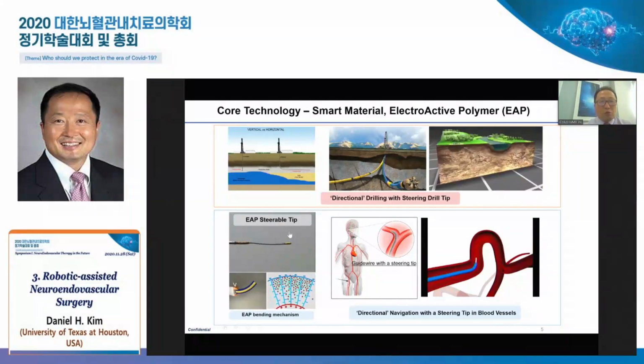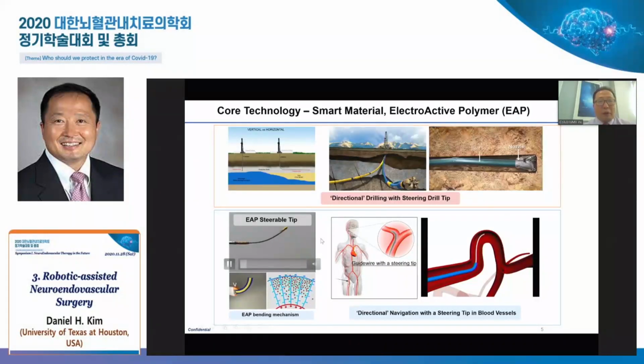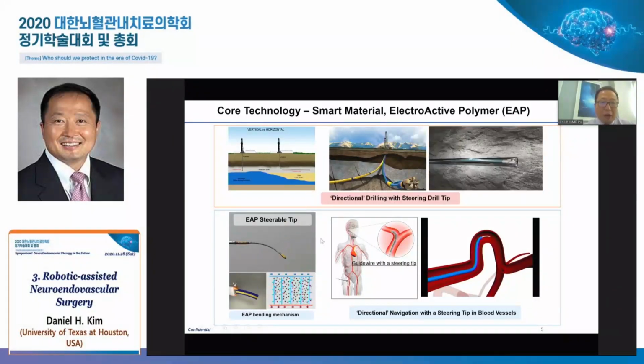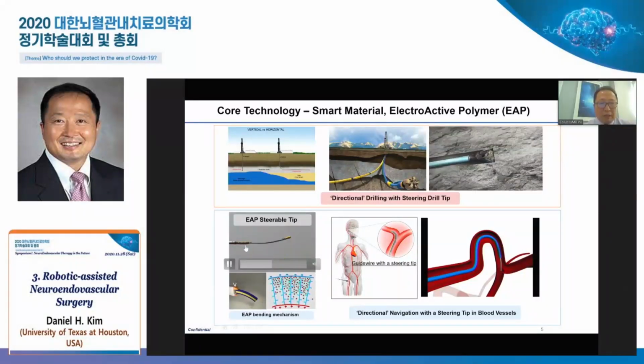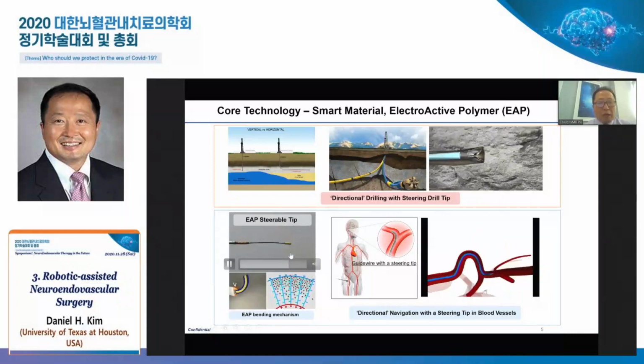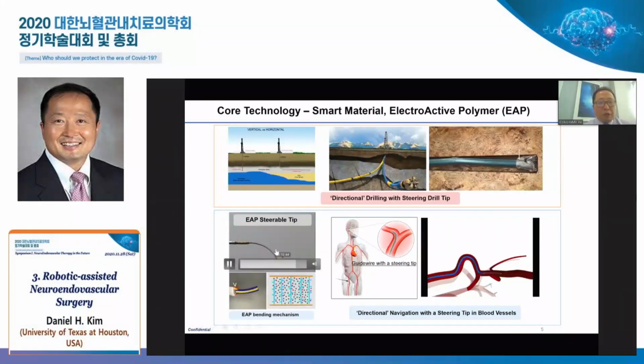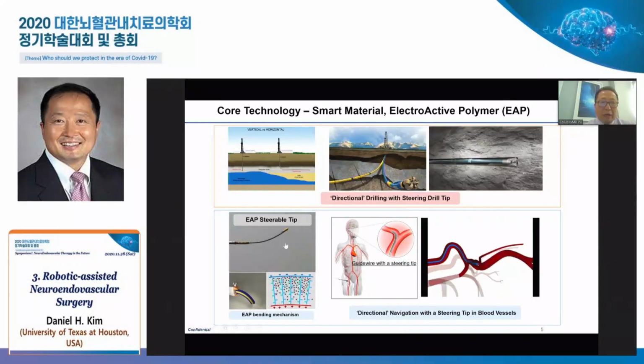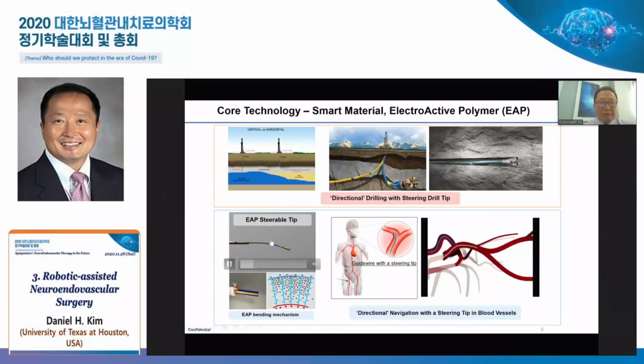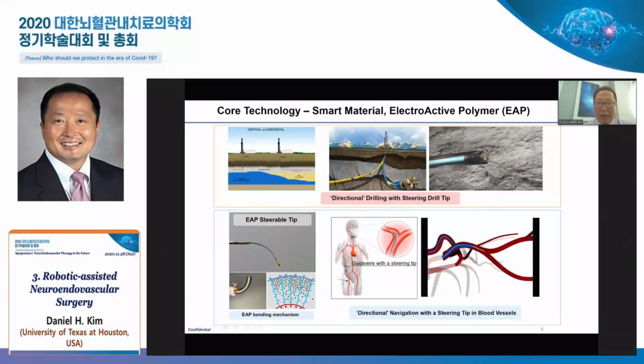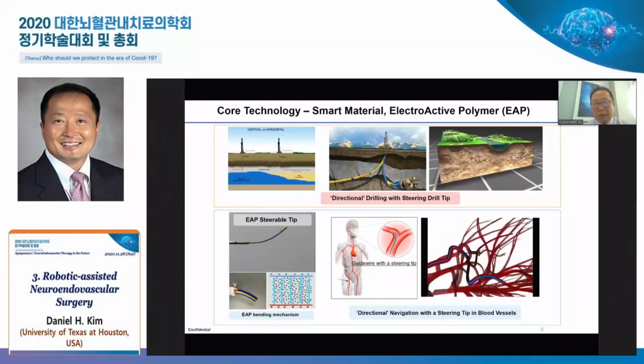So we use what we call electroactive polymer. This is an ionic polymer composite material with electrically integrated that again, on demand, we can actually actuate the predictable degree of bending at the tip. And only the tip is active. The rest of the guide wire is passive. So you can constantly navigate through tiny branches and complex anatomy.